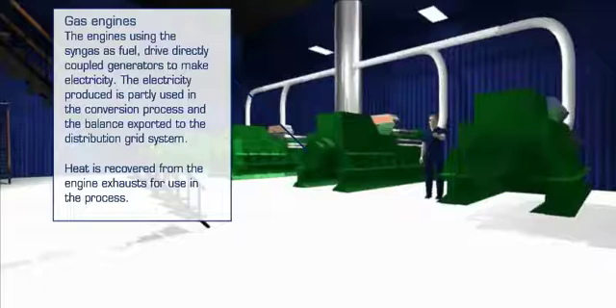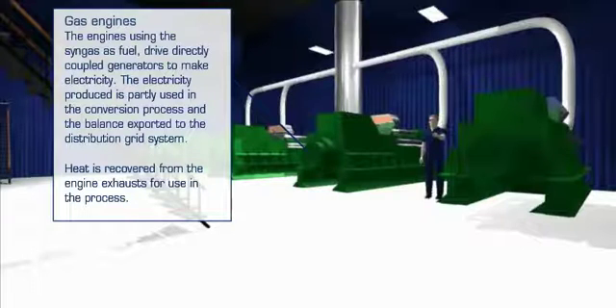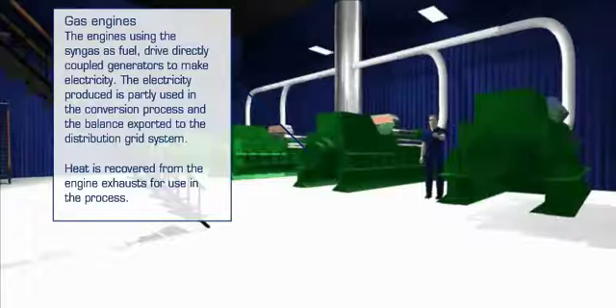The syngas flows into the engines at a constant pressure with the required rate matched to demand. The engines generate power at 11,000 volts. The power is routed to the internal distribution system with the surplus power sold on to the national grid. Each gas engine will be housed in its own enclosure, which will have both acoustic control and fire suppression systems built in to provide a secure environment for each generating set.